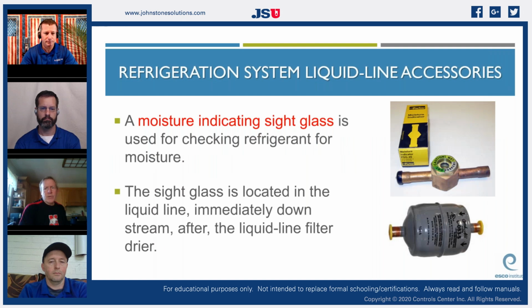We used to have a lot of sight glasses in systems. I don't know if they're as prevalent anymore. Not as much. They used to be used a lot with thermal expansion valves as a way to check the charge, kind of clear the sight glass. In the old days, you'd block the coil off to 280 pounds and clear the sight glass. Believe it or not, that was a way we used to charge systems back in the day.